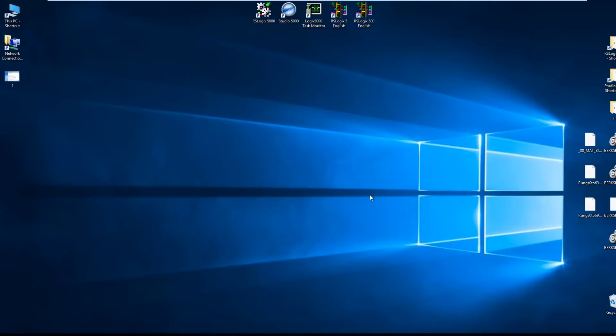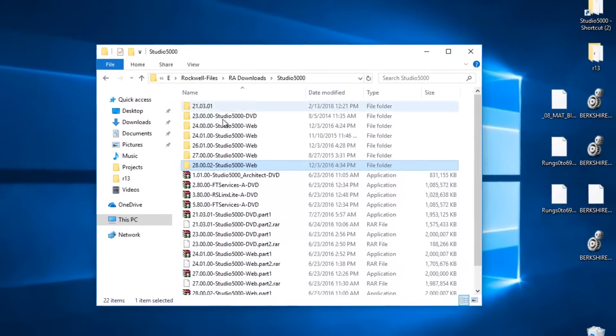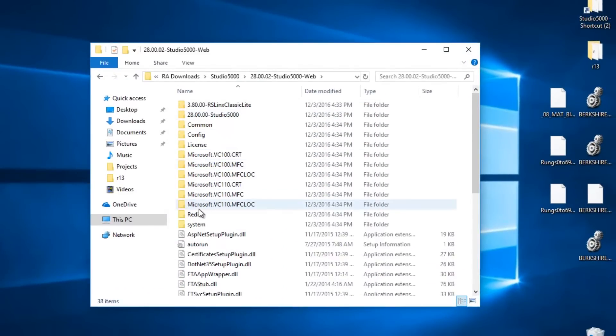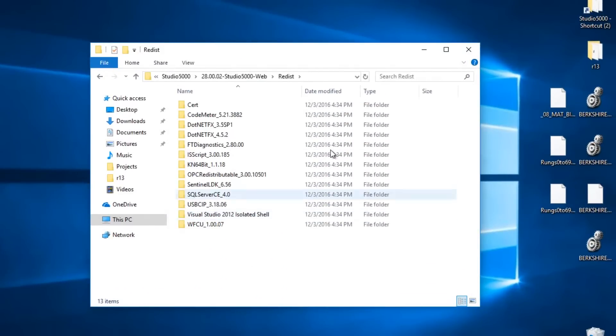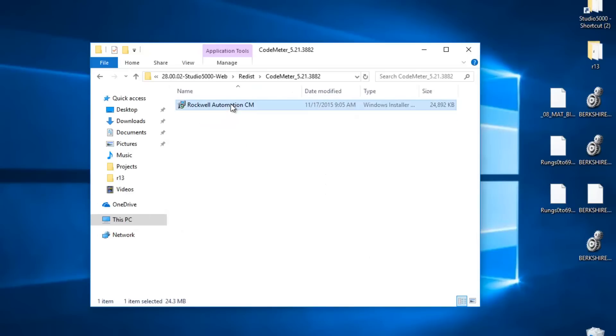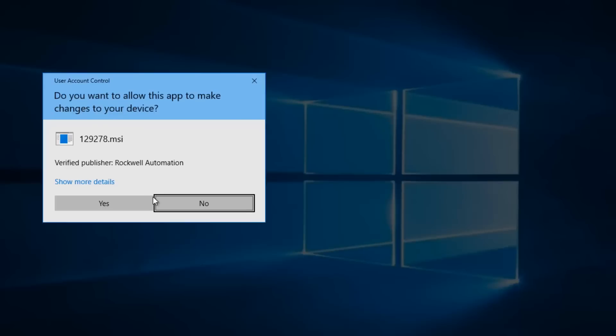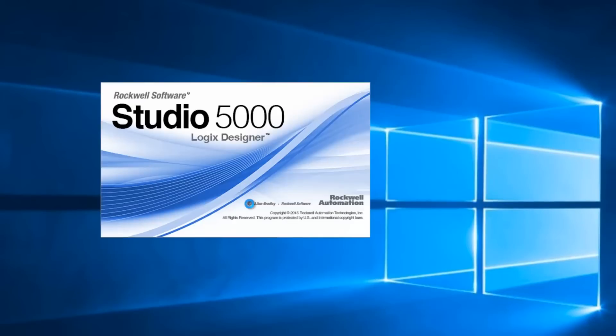So to fix that, I closed Studio and then I browsed the Studio installation files for the newer version of Studio I was trying to use and I found the CM Runtime install file in the code meter folder. And after I went ahead and installed it, newer versions of Studio 5000 worked again.